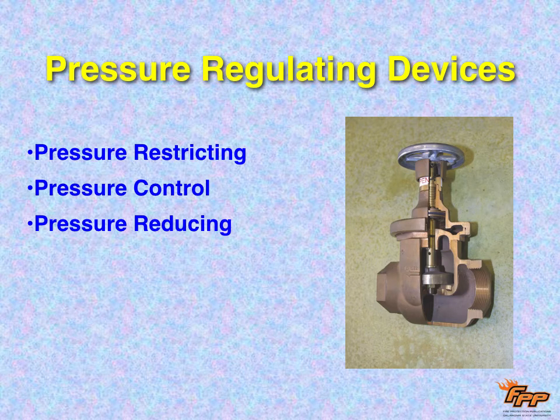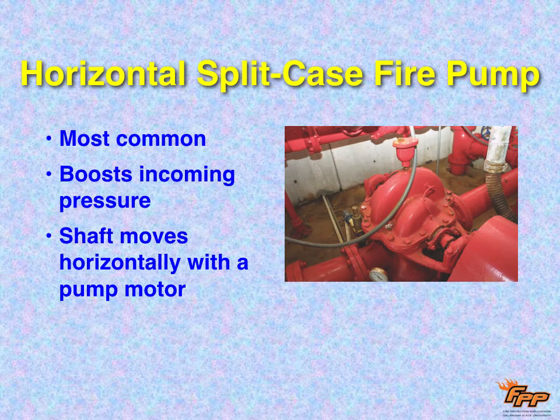Because these are used a lot in high-rise buildings, a lot of them have to have pressure-restricting or pressure-control devices, because at the different elevations we're going to have different pressure, based on gravity from tanks on the top of the building, having too much pressure as it goes down. So we have these regulators. Now, the problem with high rises is getting the right pressure and the amount of water to the higher floors. So usually, well, always, they're going to require fire pumps in conjunction with the sprinkler system and the standpipes. And there's a lot of different kinds.